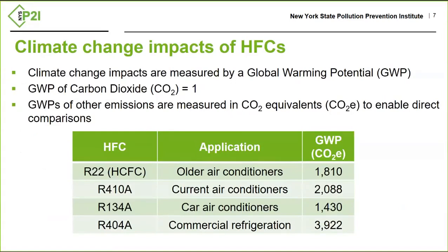So we've made a table here that includes HFCs, and actually the first one in the table is R22, an HCFC, where they're used, and their global warming potential, as I mentioned, measured in carbon dioxide equivalents. And we can see that relative to carbon dioxide, these HFCs and HCFCs are extremely higher. Used in older air conditioners, current air conditioners, car air conditioners, and commercial refrigeration.